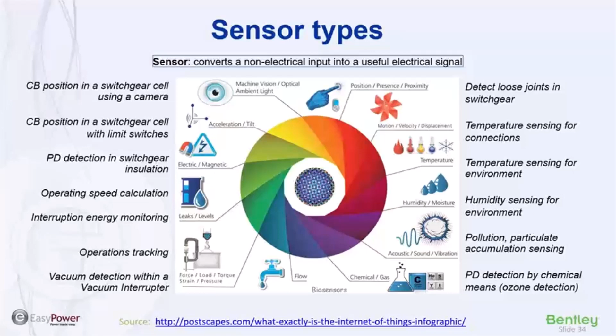On this chart, you will see basically there are a lot of different parameters that can be monitored, and when we specifically get into switchgear, what we have normally concerned ourselves with is temperature in the switchgear at key points, humidity inside the enclosure, presence of partial discharge, which is indicative of a breakdown of the insulation, and all manners of mechanical and electrical performance of a circuit breaker, right? So opening time, closing time, cumulative damage. So there are basically sensors available, right? And actually, we have multiple options of sensors for each of those parameters.